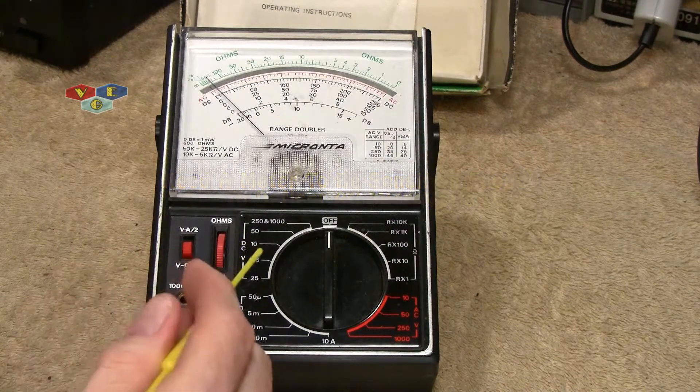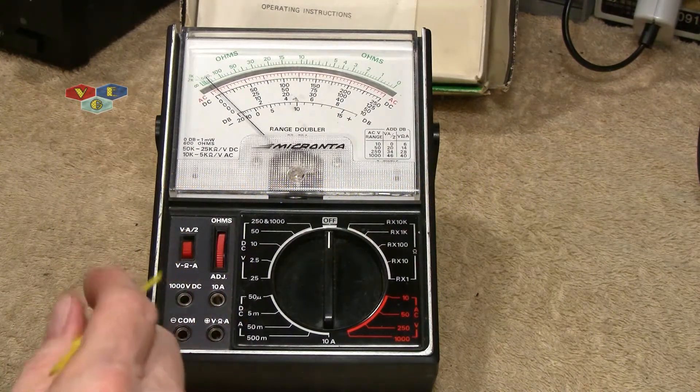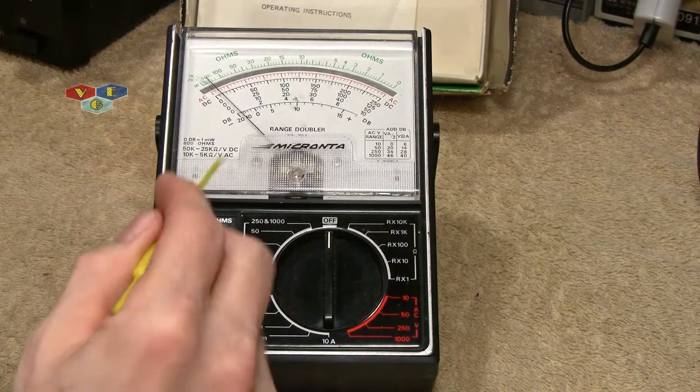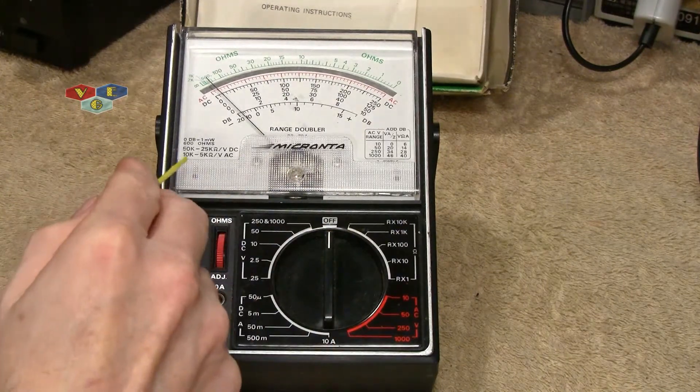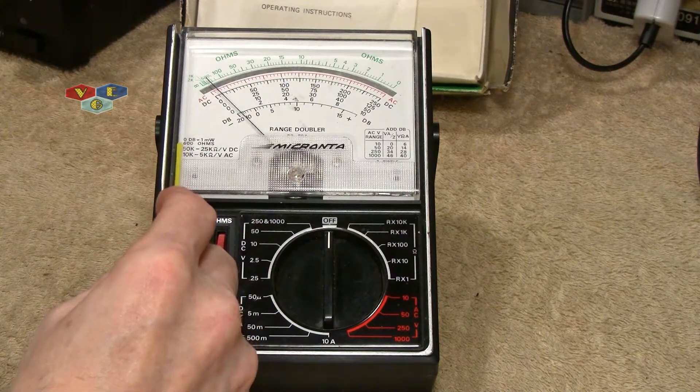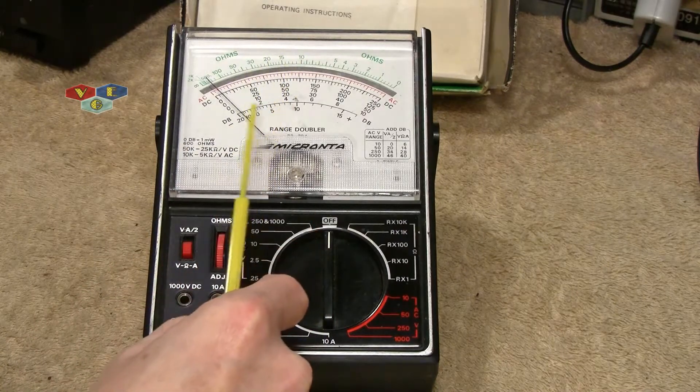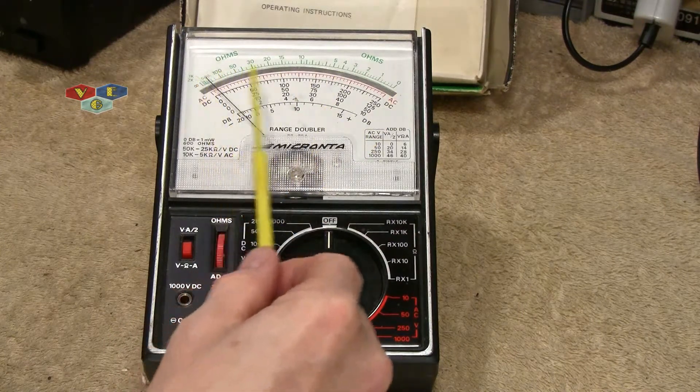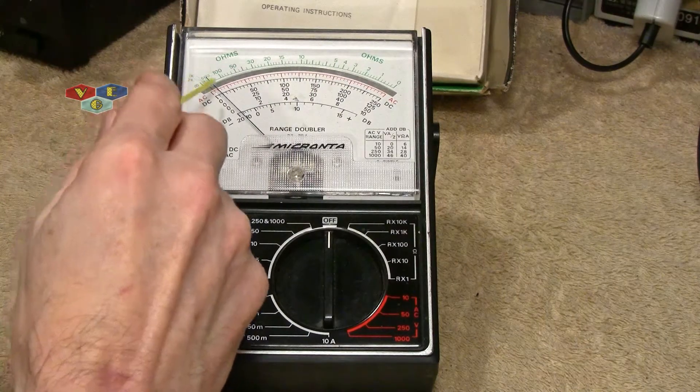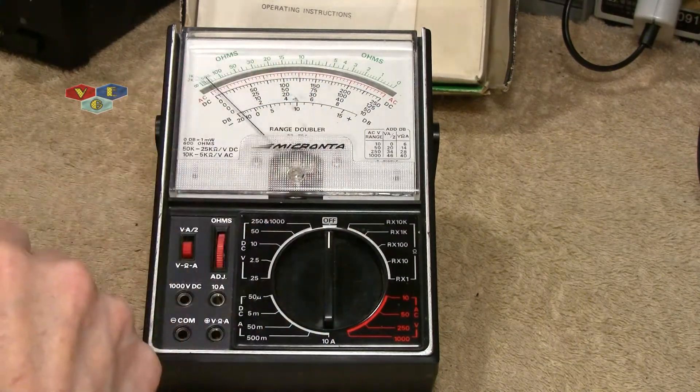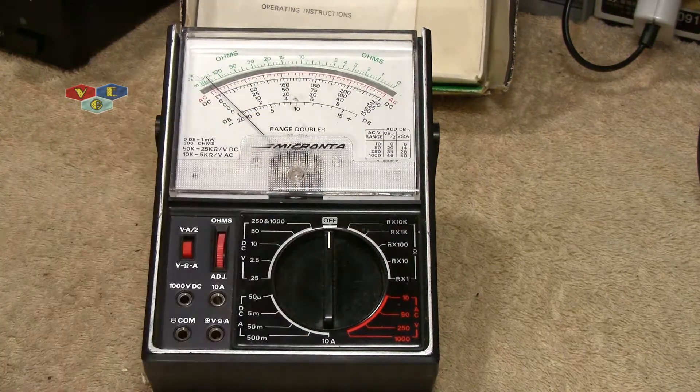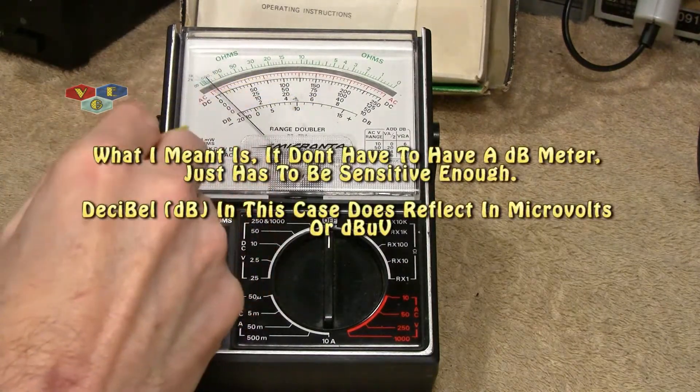For this scenario generally a VTVM is what's required, vacuum tube volt meter, but this will work. This is 600 ohms as you can see right there. We also have a DB gauge and we got a pretty little mirror to look at ourselves. Now that's to help calibrate the meter or get a better accurate measurement. And so that's really the only reason why I bought it, 600 ohms DB meter, get the right tool for the right job right.